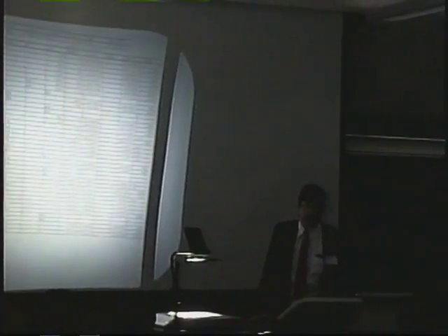ERA is a company known as Environmental Resource Associates, and in order to ensure the quality of our work, what we've got here now is a technician who says they made a solution that's 100 parts per billion. And the regression says, yeah, it's 100 parts per billion. But it might actually be 80 parts per billion, and it's real linear, and the regression still is off. The line's good. It's a good straight line, but there's no reason to believe that it's necessarily anchored at 100 and 1200 without measuring something that we know, something outside of what we put into the system that we know has a particular concentration.